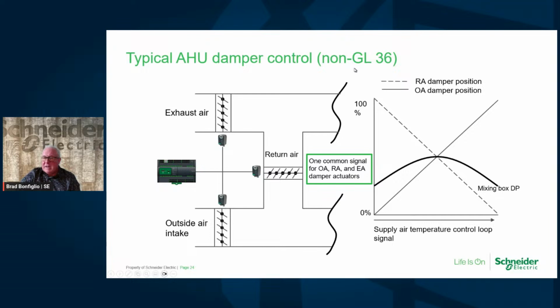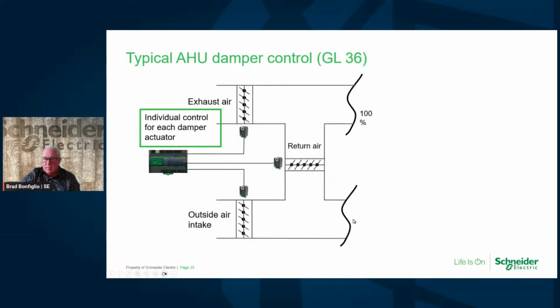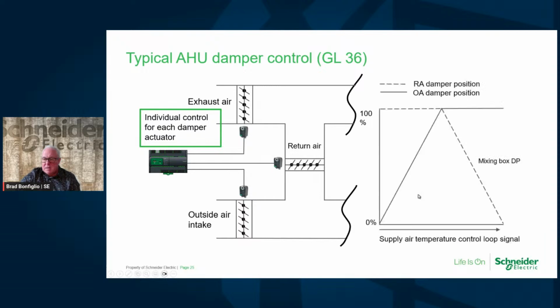Okay, so let's look at what Guideline 36 does for outside air control. It looks at it as each individual damper actuator having its own output from the controller, which means 3 outputs instead of 1. And you're going to control each one of these independently. The idea is that you're actually changing what it looks like in the mixing box area, right? So now you're getting less differential pressure buildup and you get better control. And one way to look at this is, if you think about opening the outside air and exhaust air as being proportional, well, not necessarily.